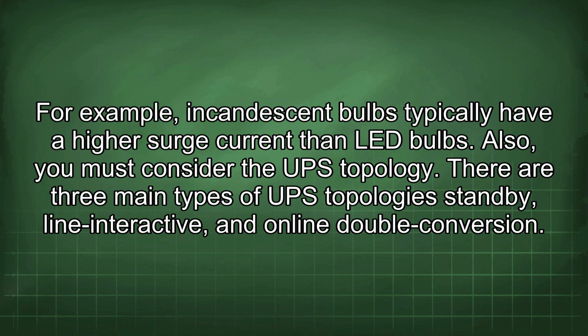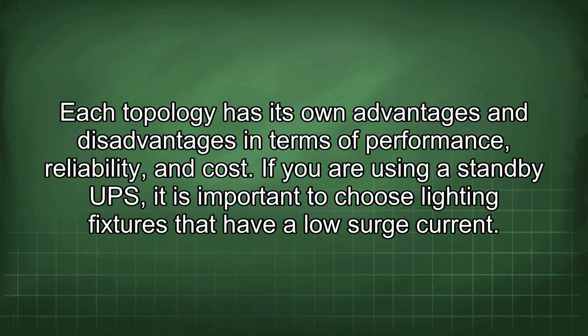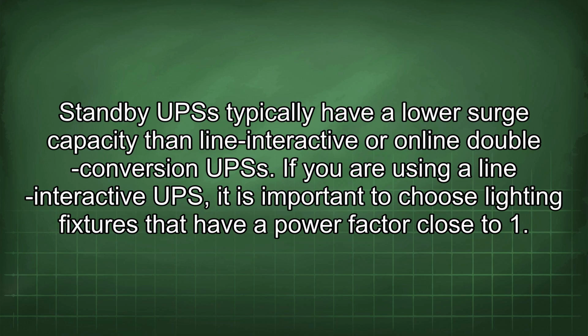Also, you must consider the UPS topology. There are 3 main types of UPS topologies: standby, line interactive, and online double conversion. Each topology has its own advantages and disadvantages in terms of performance, reliability, and cost. If you are using a standby UPS, it is important to choose lighting fixtures that have a low surge current. Standby UPS typically have a lower surge capacity than line interactive or online double conversion UPS.